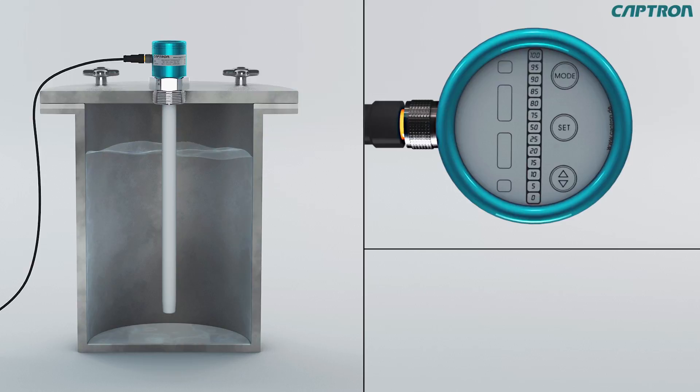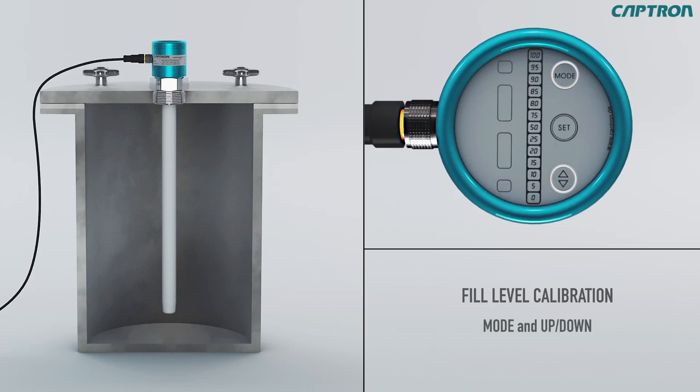In order to adjust the fill level, we go now to the adjustment mode. Touch mode and up-down at the same time for approximately 5 seconds until the 0%, 100%, as well as MIN light up. Now let go of all the buttons at the same time. The last set minimum value will blink. Now the probe will jump automatically to the minimum alignment.